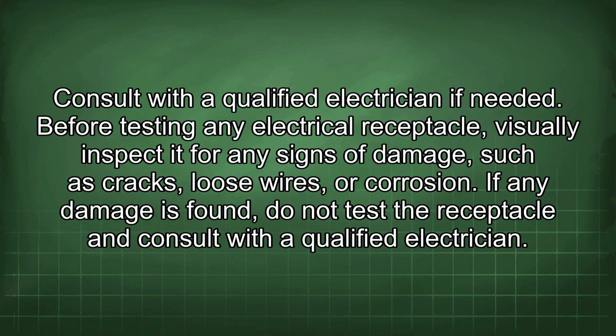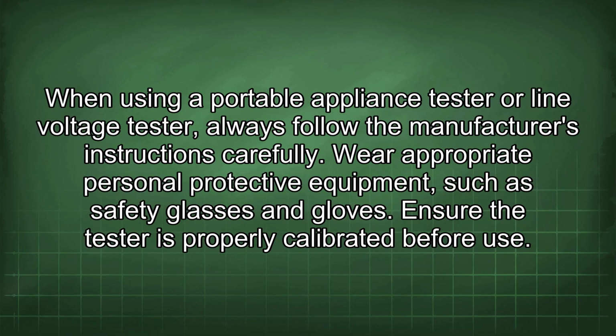Before testing any electrical receptacle, visually inspect it for any signs of damage such as cracks, loose wires, or corrosion. If any damage is found, do not test the receptacle and consult with a qualified electrician. When using a portable appliance tester or line voltage tester, always follow the manufacturer's instructions carefully. Wear appropriate personal protective equipment, such as safety glasses and gloves. Ensure the tester is properly calibrated before use.